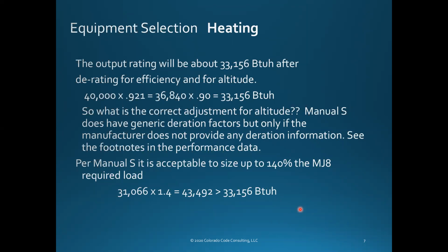Then you're actually allowed per Manual S to be 40% larger than our calculated load. So we take what our calculated load was, in this particular case just over 31,000, and take it times 1.4. That means we could have an output capacity of up to 43.5, and of course, ours is less than that. So why 40%? Well, because this is a tough target and we've got lots of different sizes. Also, oversizing on a furnace is not as critical an energy penalty as it is for air conditioning.